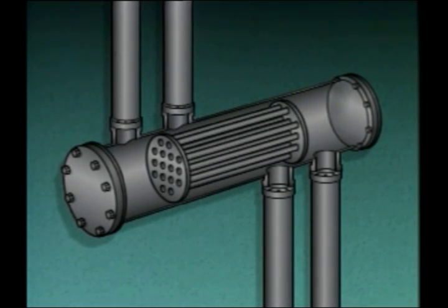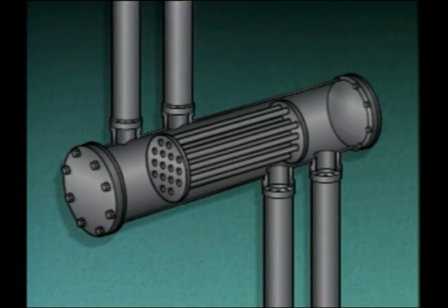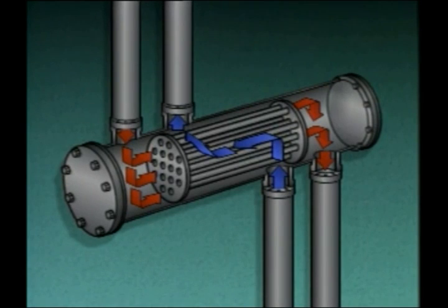The tube walls provide a surface area for heat transfer between the two fluids. Tube sheets support the tubes and help form the heads — the ends of the heat exchanger. The fluid that flows through the tubes enters and exits through the heads. In this heat exchanger, the hotter fluid flows through the tubes and the cooler fluid flows around the tubes. As the two fluids flow through the heat exchanger, heat transfers from the hotter fluid to the cooler fluid, so the hotter fluid is cooled and the cooler fluid is heated.